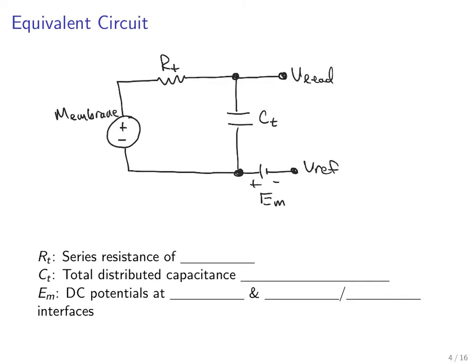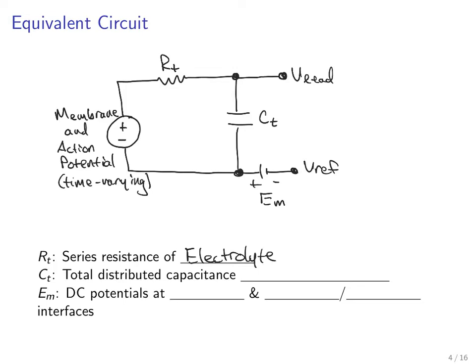And here, the voltage source represents the membrane and action potential, the sum of those two, which could be time varying. That's what we're interested in measuring. Okay, so R sub t here represents the overall series resistance of the electrolyte. And C sub t represents the total distributed capacitance, which I believe is dominated by the glass, because the glass itself acts as a dielectric. The E sub m are DC potentials at electrolyte and metal electrolyte interfaces. They result from non-uniform distribution of charge at those interfaces.